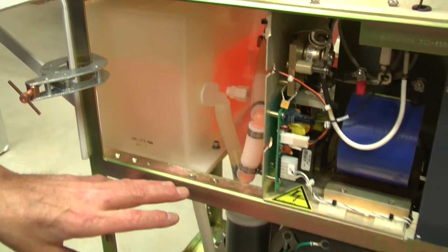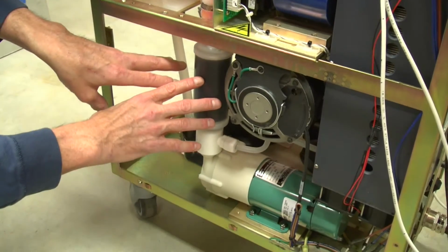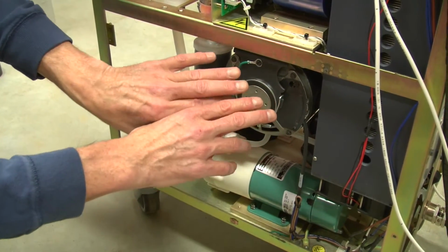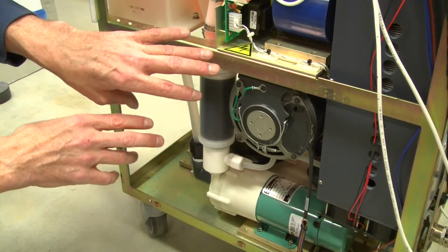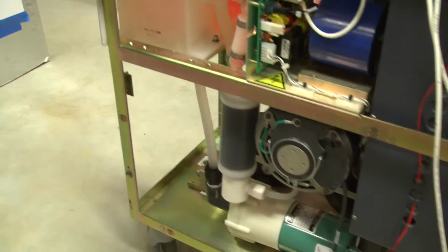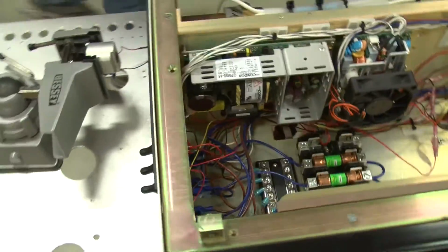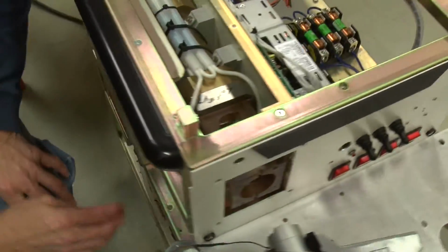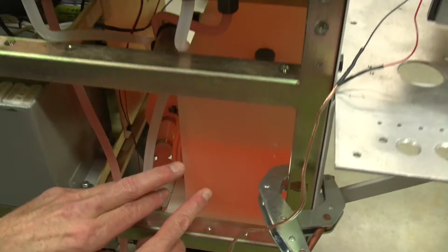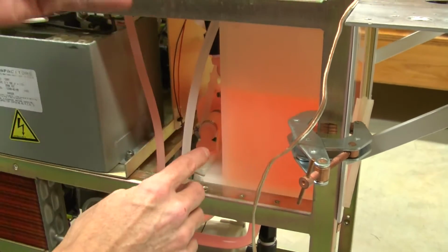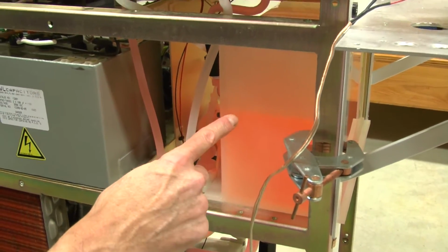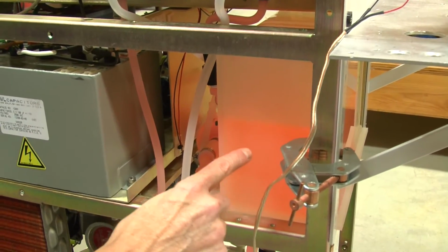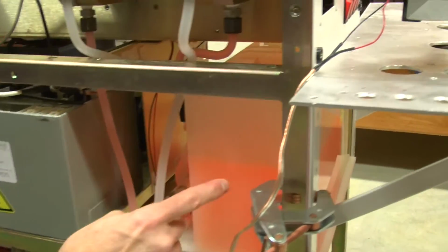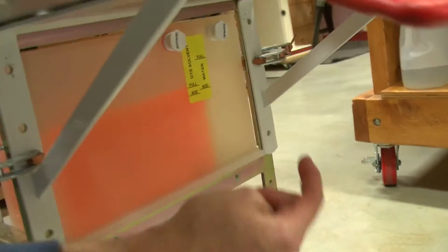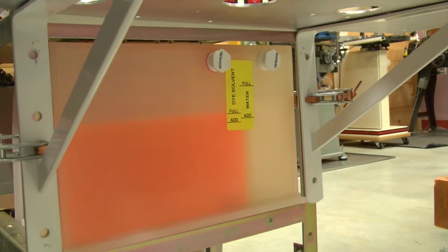Both of the flash lamps are surrounded by a jacket of water and are cooled by this system here. This motor pumps the other plumbing system, which is the dye, and I'll show you on the other side so you can get a view of that. The dye is kept in the same reservoir as the DI water. It looks like the same container, but it's got a small divider between the two. It's kind of a neat piece of engineering here. Same reservoir, but two compartments. One compartment contains the dye, the other contains the DI water, and there are a couple of fill plugs there that make it easy to replace the liquids.